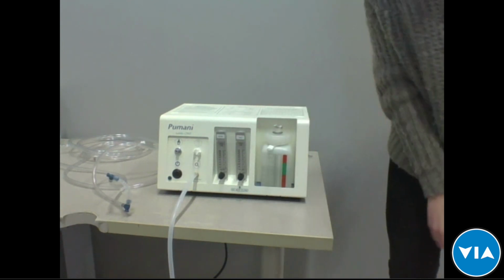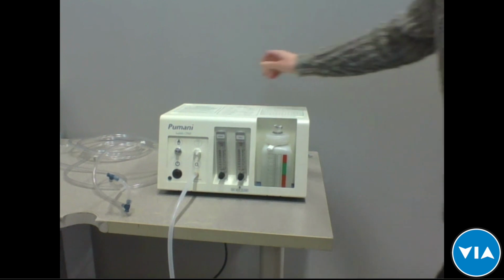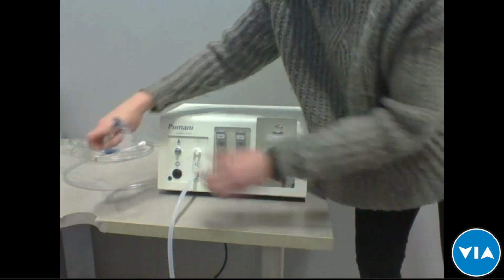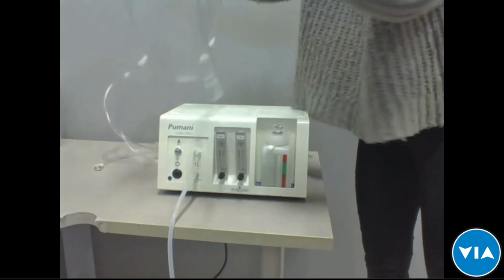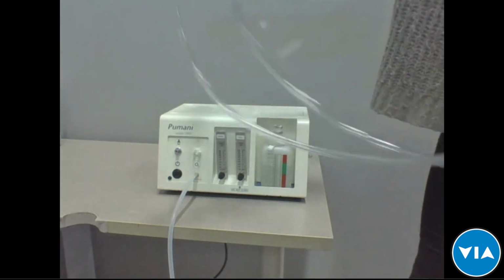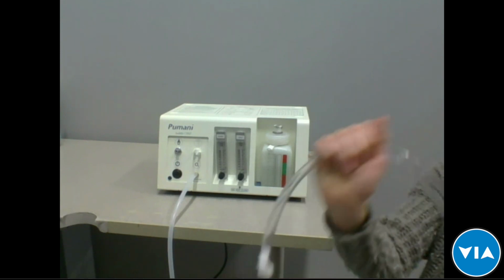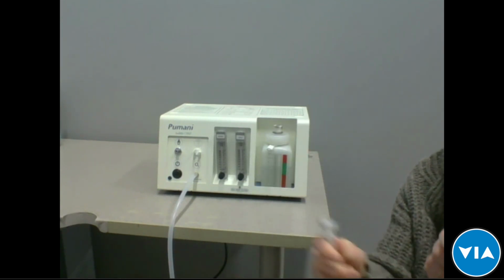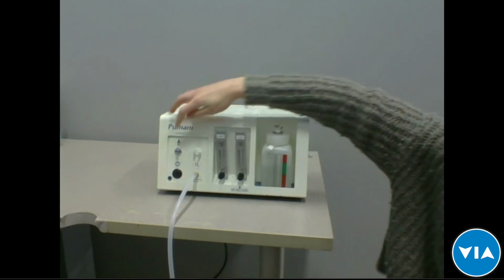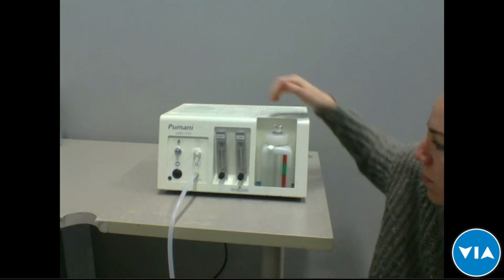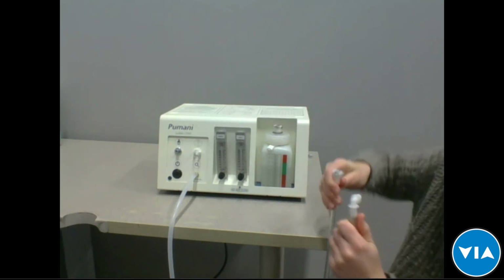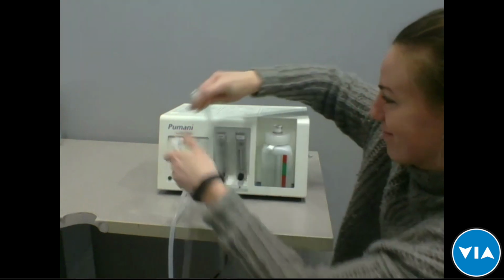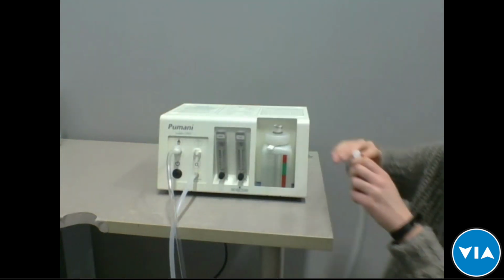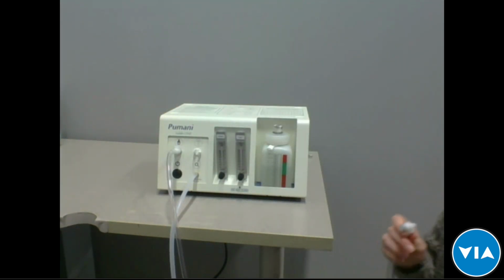And then the next step is to connect the tubing, so the inspiratory and expiratory tubing. So you have 2 long sets of tubes, and there are 2 ports. One port has a baby in front of it, it is a baby port, and that's the inspiratory tubing. And only one side fits in there, so you can't mess it up. So you snap that in there, and that's the inspiratory tubing. So that's where the blended air and oxygen go into the baby.